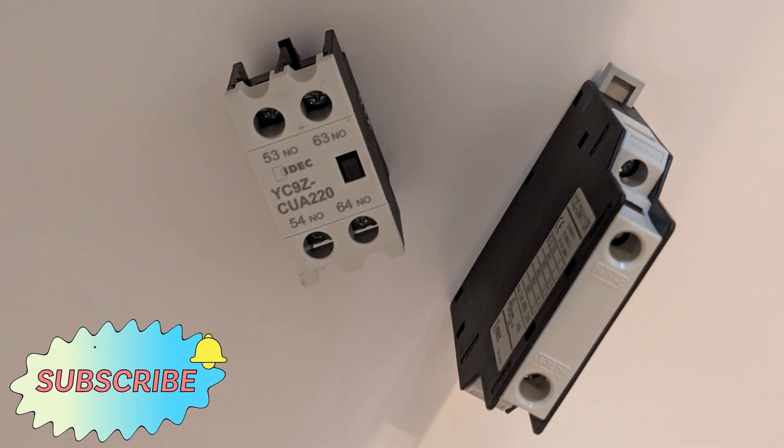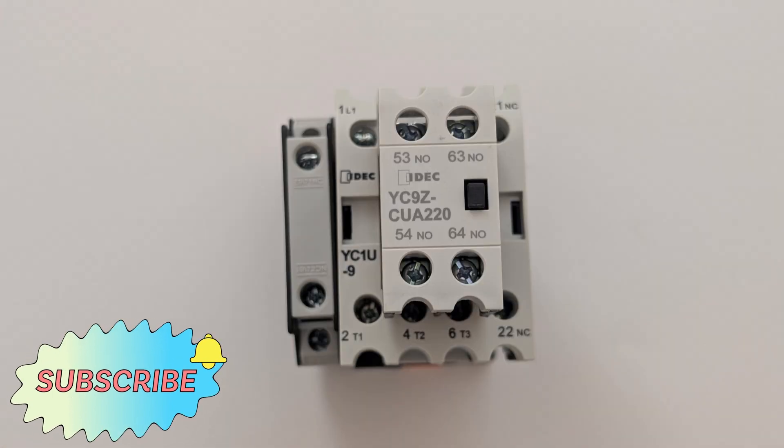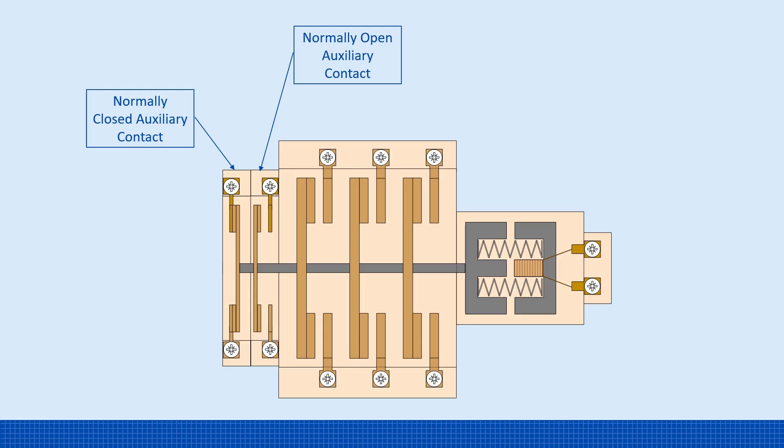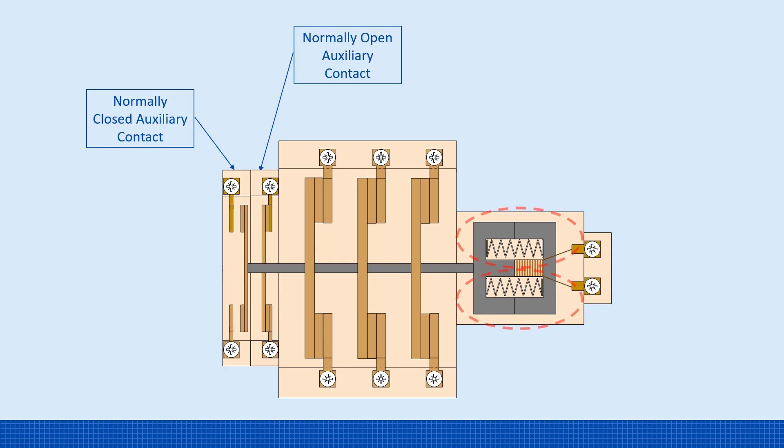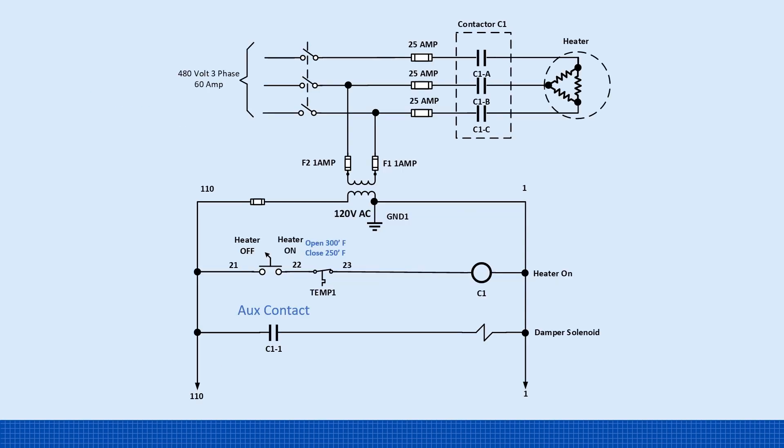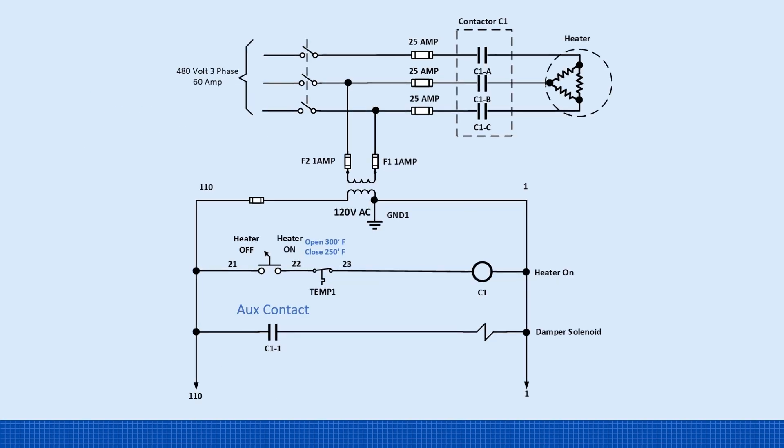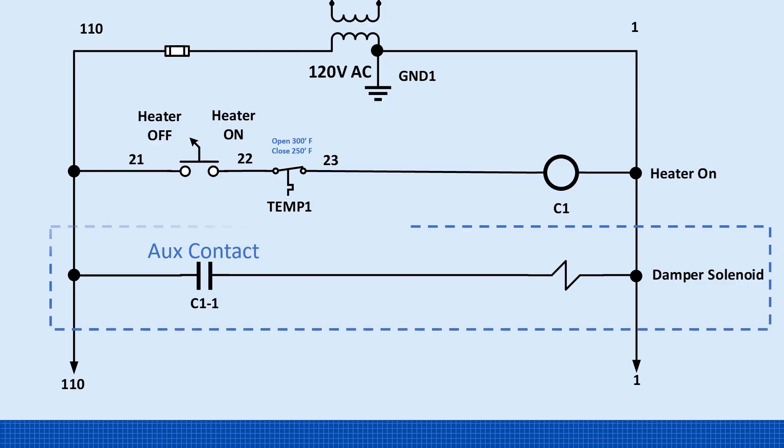So what are auxiliary contacts? Auxiliary contacts are add-on contacts that attach to the contactor. They don't carry the main load. Instead, they're used in the control circuit. Depending on whether they're normally open or normally closed, they will switch when the main contactor is closed. They're commonly used to latch a circuit or as an interlock to trigger other parts of the logic. In our example, when contactor C1 is energized, its auxiliary contact C1-1 also closes. This closed contact completes the circuit and energizes the damper solenoid.